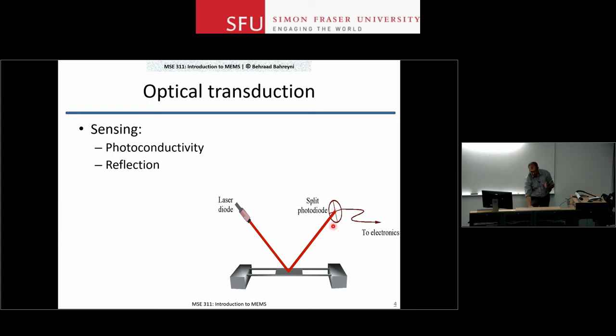And then if this device moves up and down, that light beam, or that spot of light, will move on the photodiode, and depending on the ratios of the currents that you receive from these photodiodes, you can estimate how much the device moved up and down. Extremely sensitive. With $10 of components, your laser and your photodiode, and a setup to hold all of this together, you can measure nanometers of movement with some little effort. I would say not an extreme amount of effort, but you have to be careful to get all the vibrations out. But once you do that, you can really measure nanometer levels of vibration or displacement using this technique.